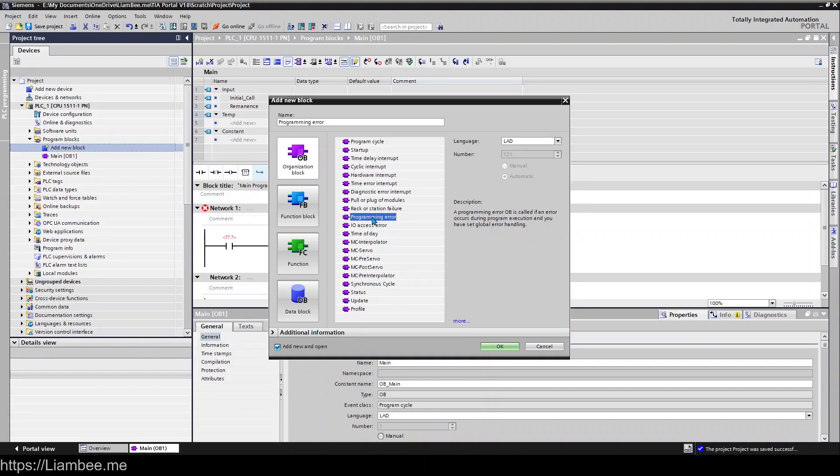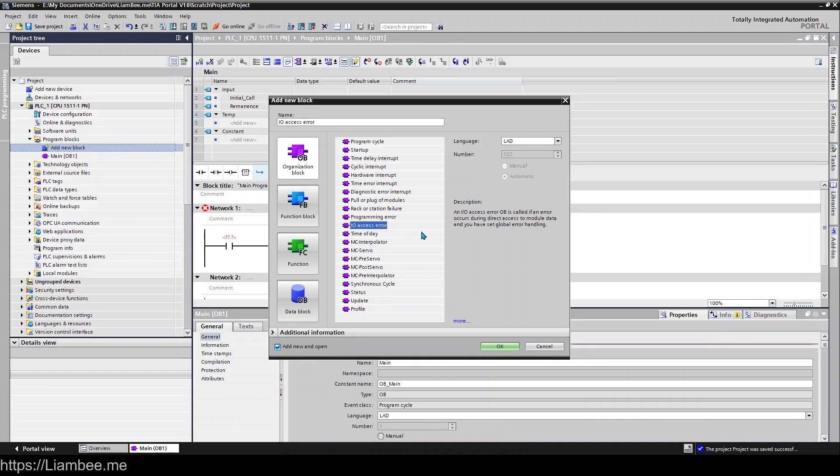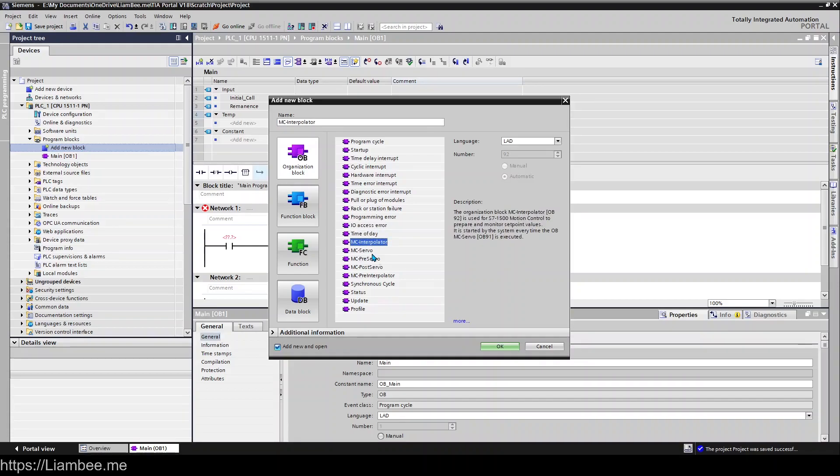Same for IO Access Error. If you've got things set up in your project for IO like we have in previous videos, set up the input and output modules. Because they don't exist, if you were to simulate this in PLC Sim Advanced for example, having IO Access Error in there stops the PLC from saying I can't access any of my IO. It is better now because the PLC knows it's being simulated. But if you had a real CPU for example you'd still get the IO Access Error, so putting this block in there suppresses that.